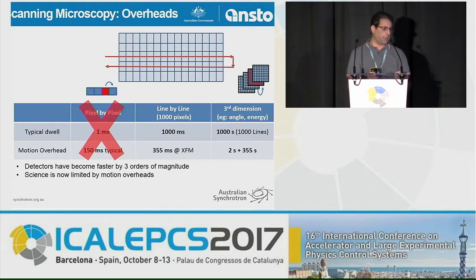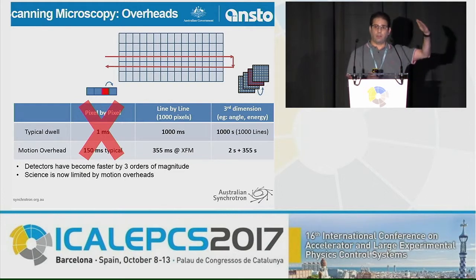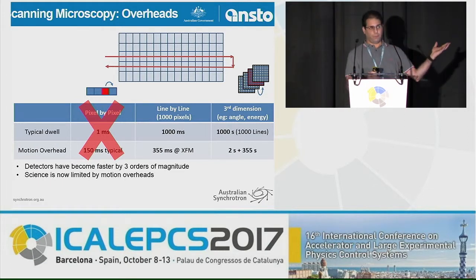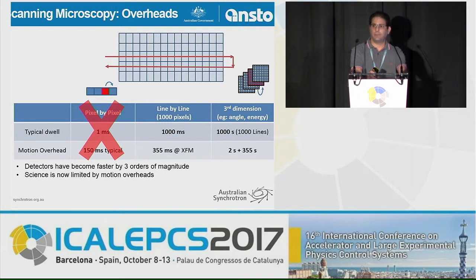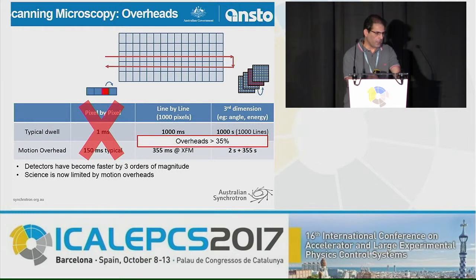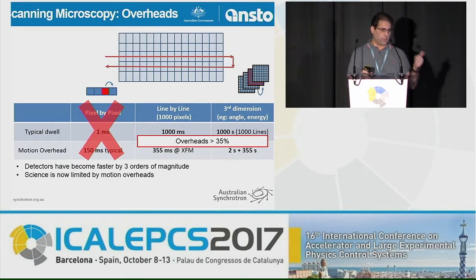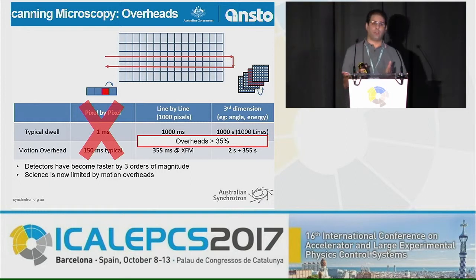In XFM, they've been using fly scanning since the beginning, what we call line-by-line scanning, because we need to scan the whole image. This consists of a fly scan over a line, then the sample stage stops, positions to the next line, starts and accelerates to the required velocity, and scans the next line. This is basically the second dimension of the scanning.